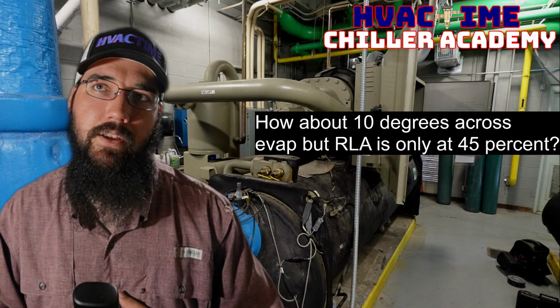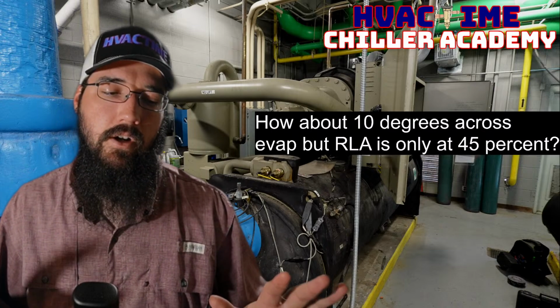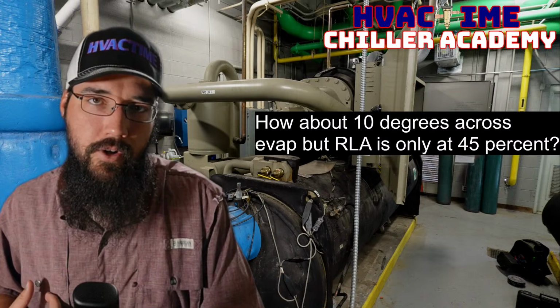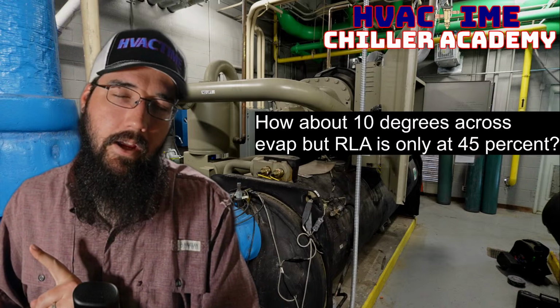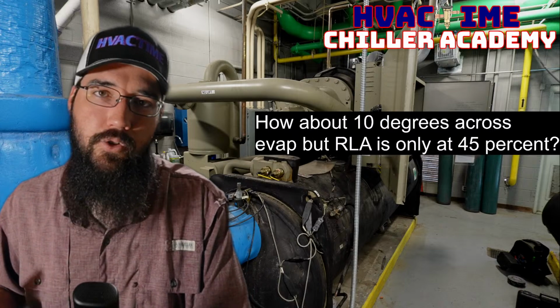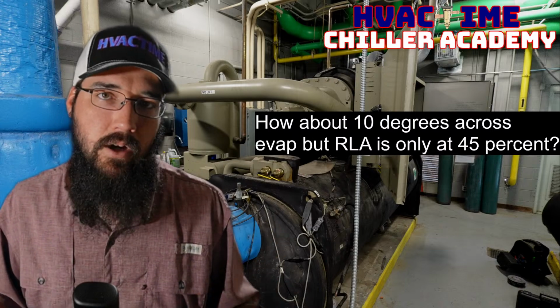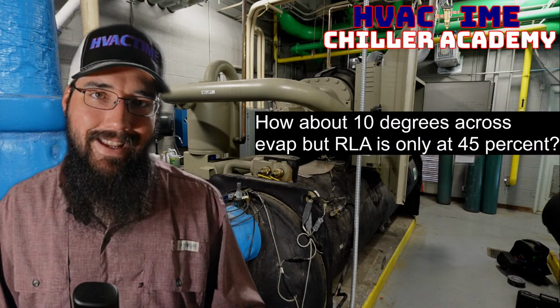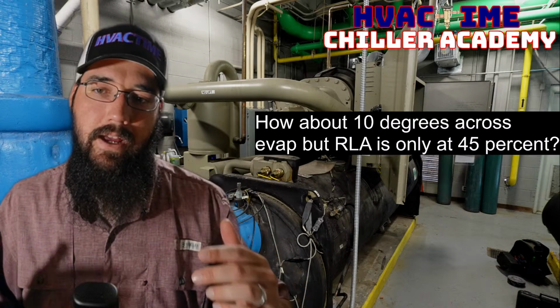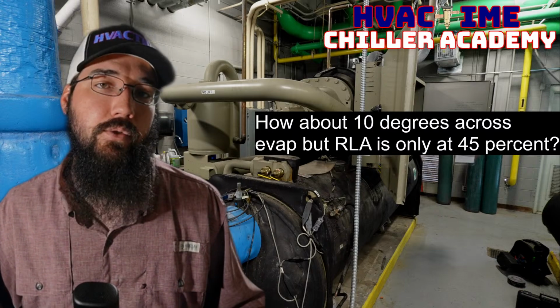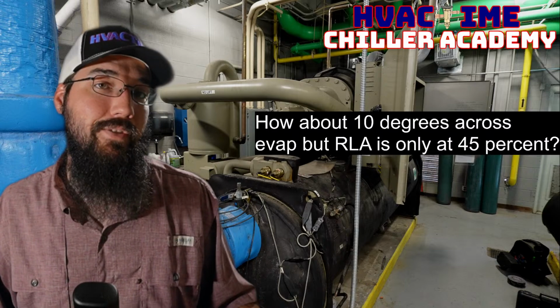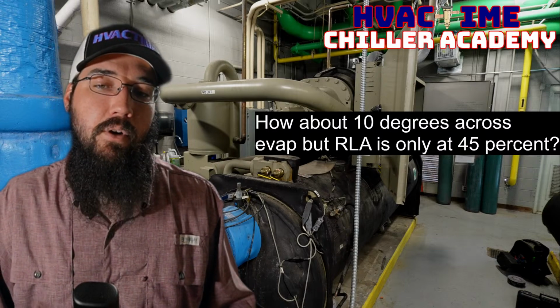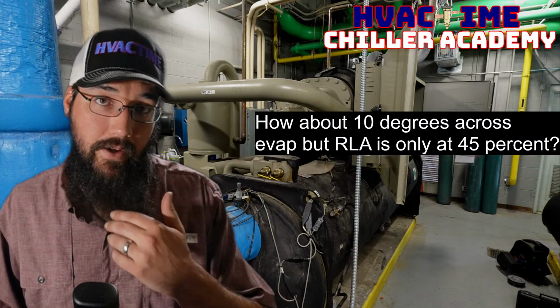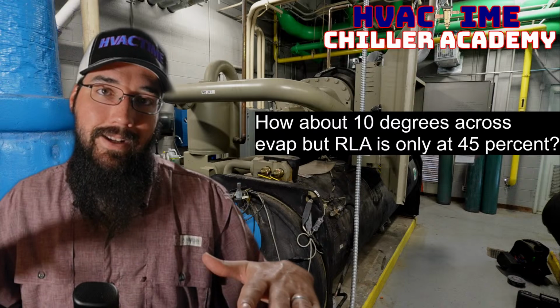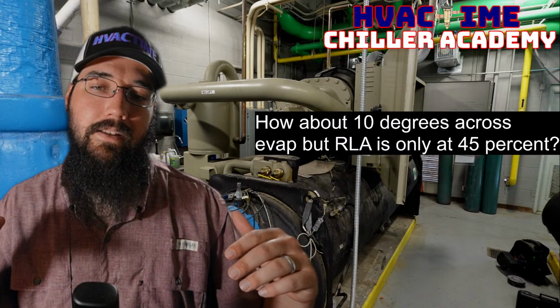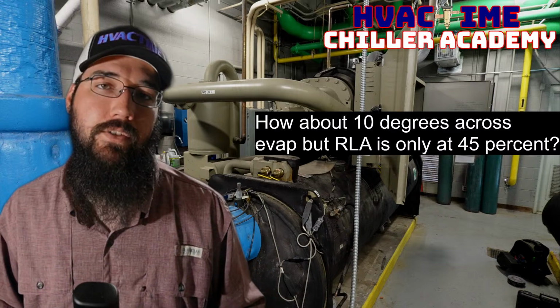So there's a couple of other things. Let's say all the other conditions are absolutely perfect. We know that our GPM, our charge, and our tubes, all of that is in a good state. We have proper heat transfer. This condition can still happen, and it'd be perfectly normal, where we've got a 10 degree across but our compressor is only pulling 45% RLA, which would mean that we've got a loaded machine, but yet our motor load is quite low. Well, there's two other things that affect this. It comes down to lowering lift. So I don't have that kind of data, but just things to consider.